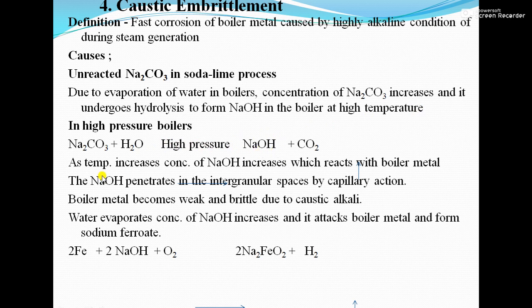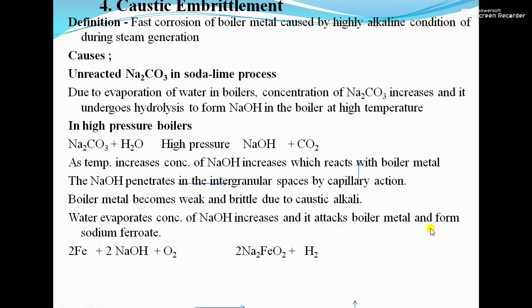As temperature increases, evaporation of water takes place, so the concentration of NaOH increases. This NaOH reacts with the boiler metal to form sodium ferrite. The NaOH penetrates into the inter-granular spaces by capillary action, making the boiler metal weak and brittle due to the caustic alkali. As water evaporates, NaOH concentration increases further and attacks the boiler metal to form sodium ferrite.